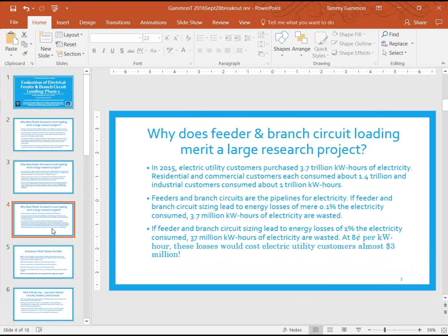The other issue, which I included because I know it's one of your big interests, is whether improperly sized equipment introduces additional safety hazards — specifically higher available fault currents and additional arc flash hazards.